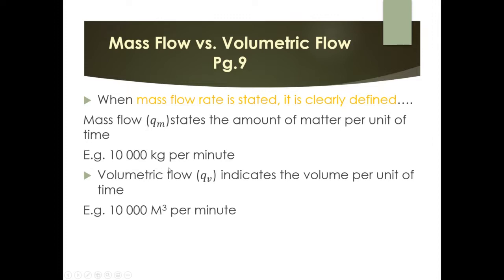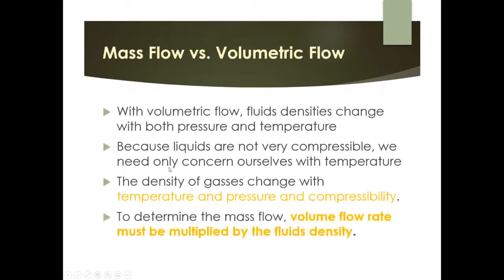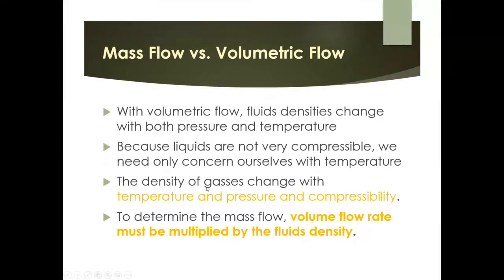The key difference with volumetric flow is that fluid densities change with both pressure and temperature, and also compressibility. For liquids, which are not very compressible, we usually only concern ourselves with the temperature component. For gases, the effects of temperature, pressure, and compressibility are all significant — that's the key distinction between liquids and gases, both still called fluids.